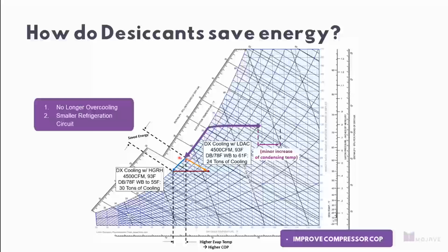Now, going to my comment about reducing refrigerant and being a decarbonization product, we're also shedding this portion of the refrigerant and compressor capacity by leveraging liquid desiccant. So on average, our systems are about 33% smaller on the refrigeration circuit, saving you a significant amount of energy. And that energy saved typically ranges between 40 and 60%. The reason for that, going back to my example, is you work harder for every degree colder you push your subcool on a coil. So your compressor spend is an exponential curve, again, diminishing returns. So by eliminating that portion, we save 40, 50, 60% of the energy spend in dehumidification by leveraging this passive process.